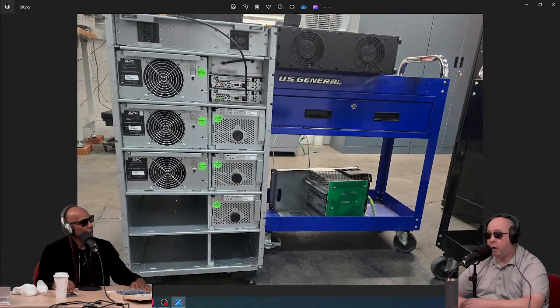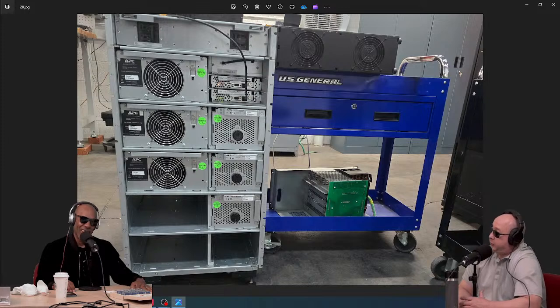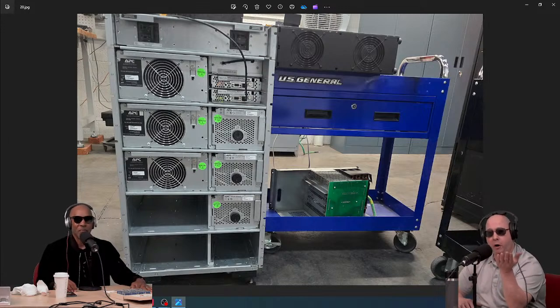Why? This is what the customer wanted, this is what the customer ordered. They have 3 power modules, so it's a 12 kVA unit, and 3 backup batteries. Now this has the capability to be a 16K unit with a redundant backup power module in case one fails — the redundant takes over — and it has capacity for 4 batteries also. And then, just like the PX, the LX can have external battery cabinets for additional runtime.